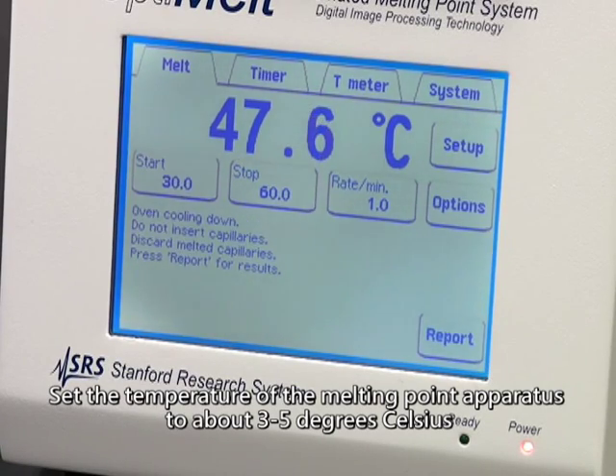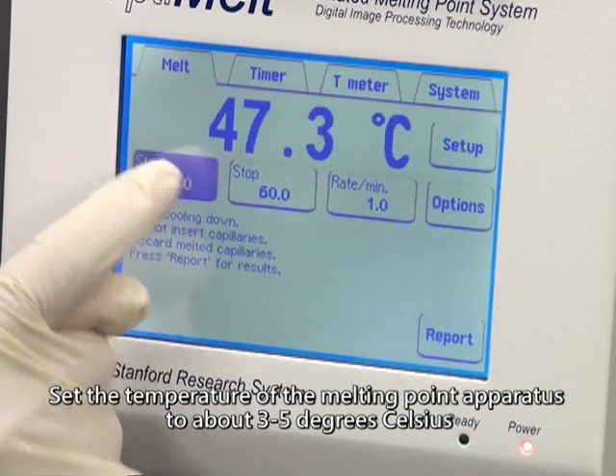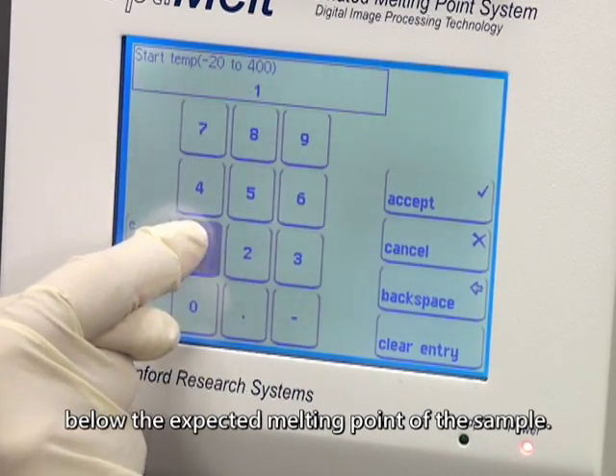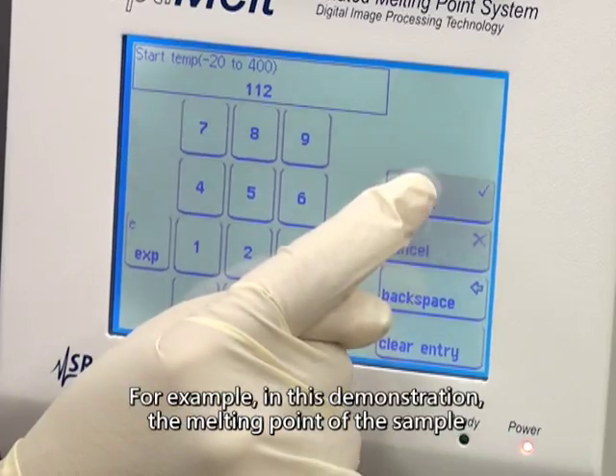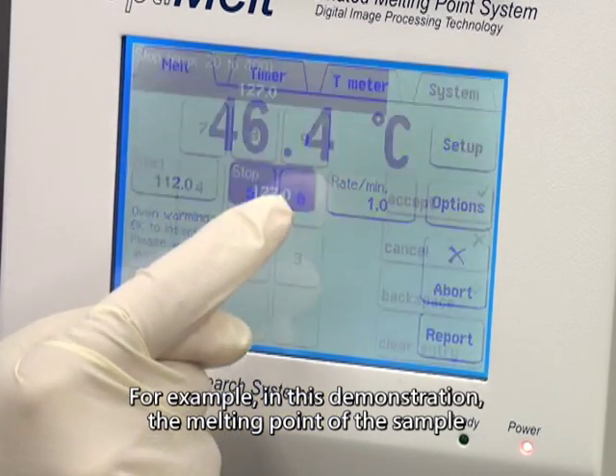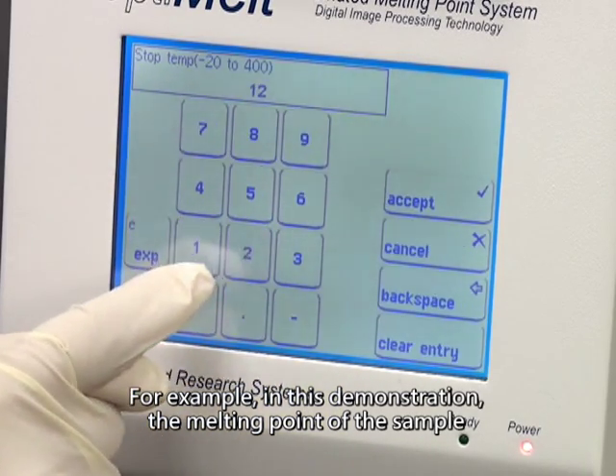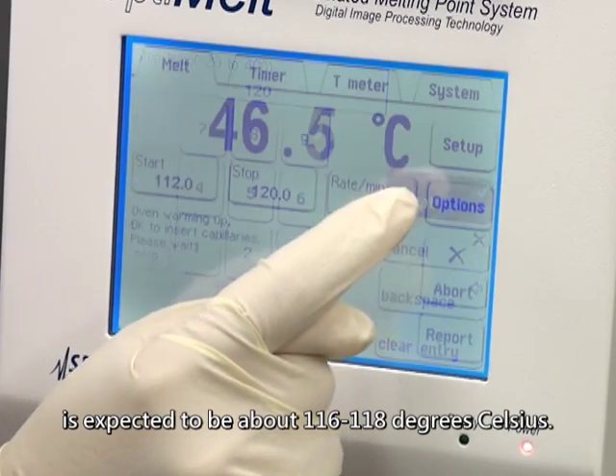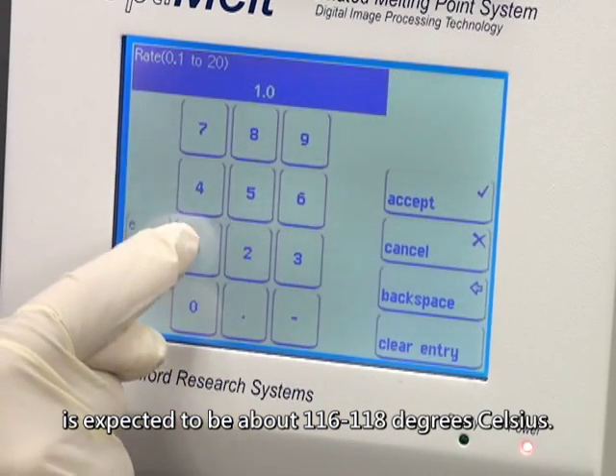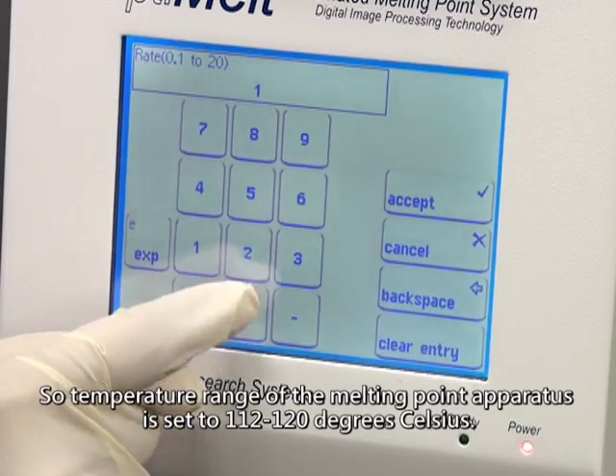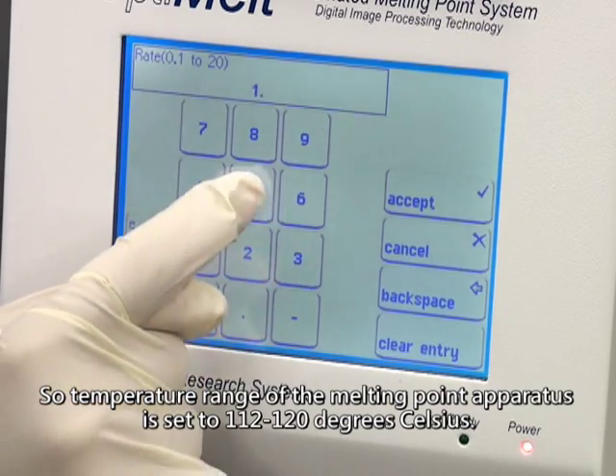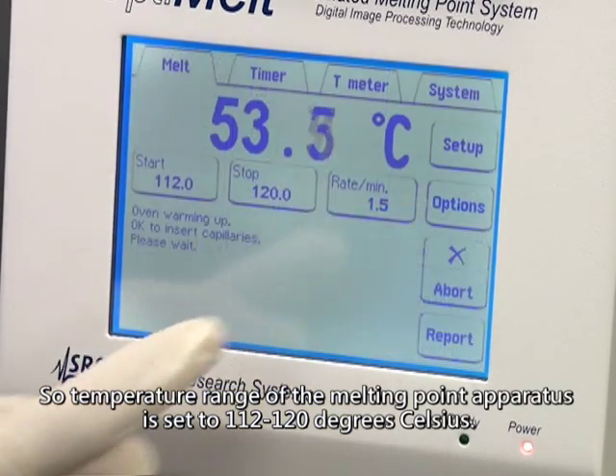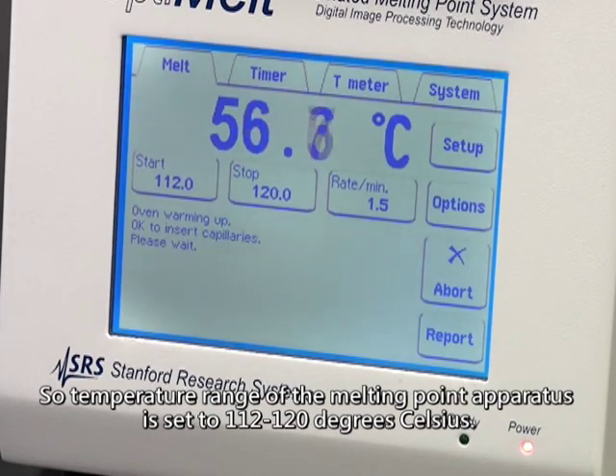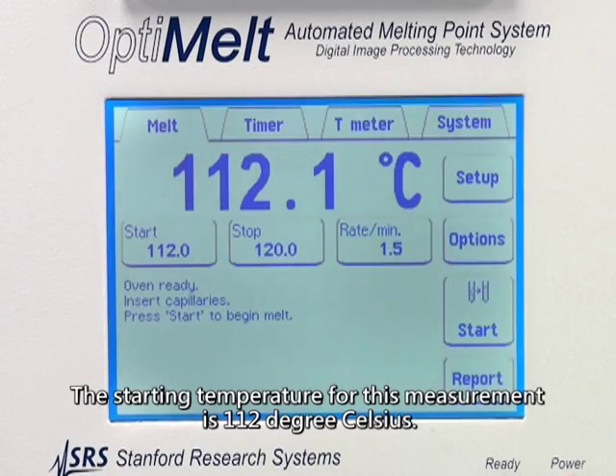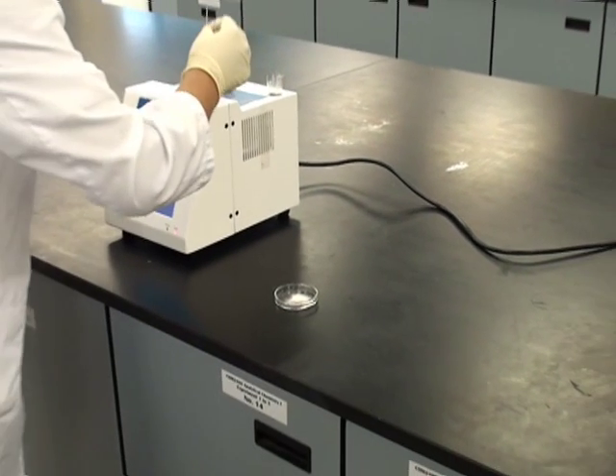Set the temperature of the melting point apparatus to about 3 to 5 degrees Celsius below the expected melting point of the sample. For example, in this demonstration, the melting point of the sample is expected to be about 116 to 118 degrees Celsius. So the temperature range of the melting point apparatus is set to 112 to 120 degrees Celsius. The starting temperature for this measurement is 112 degrees Celsius.